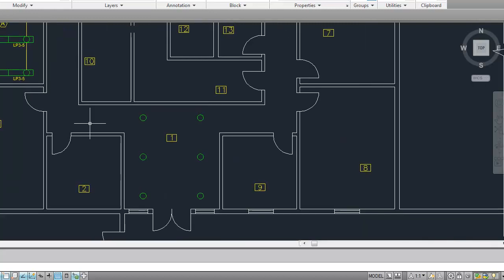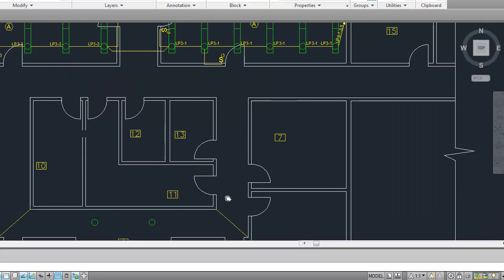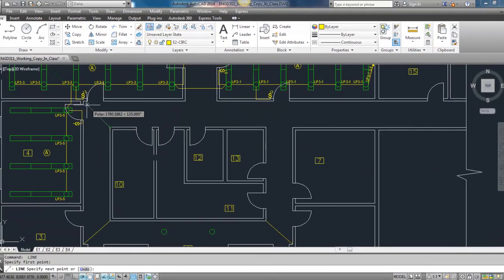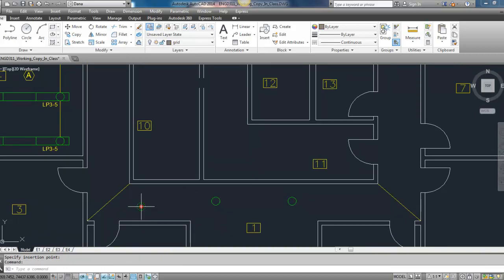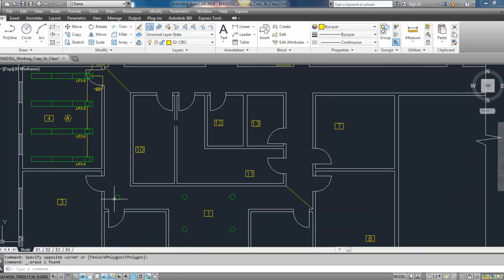So the best way I think to do the hallway is to start with the corners. I'm going to draw a line in the corners, because I want to be able to find the midpoint of those corners. I won't worry about this one for now, but I want to take one of these luminaires and place it in the midpoint of that particular one. Now you could do an X here, but essentially I'm doing the same thing. I'm placing that as close to the corner as possible.